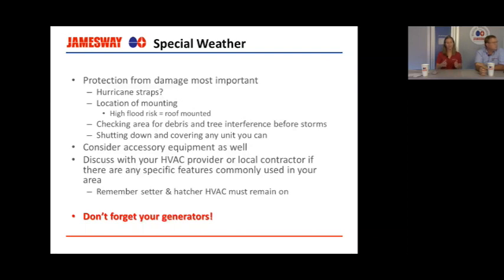One final problem with it is if your hatchery is setting room 1 in week 1, room 2 in week 2, and room 3 in week 3, 100% fresh air will not do it for you. And the reason for that is in week 1, in each of those rooms, 0 to 10 days, your dampers are closed. You have no fresh air requirement into the room. Therefore, you have no air requirement into the room in a 100% fresh air situation. And what happens then is the heat off the incubators and hatchers heats the room up. And we've seen rooms hit over 90 degrees Fahrenheit just from the heat off the incubators and hatchers heating the room, or just the incubators in that 0 to 10 day period.